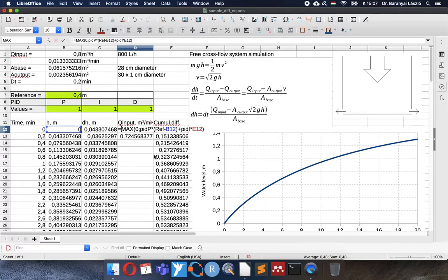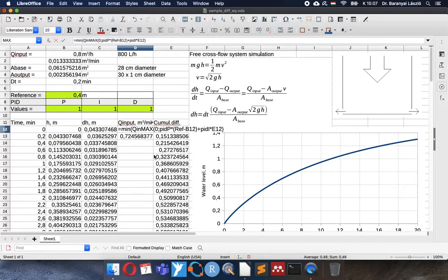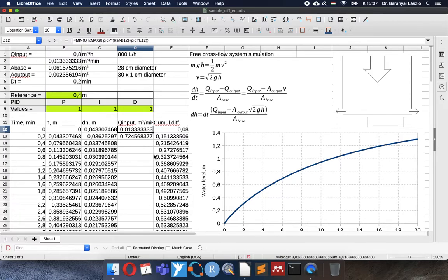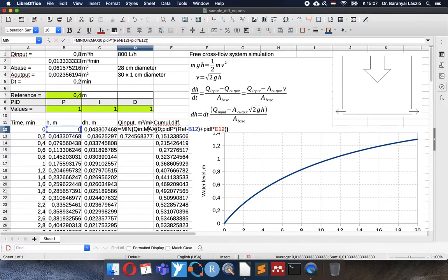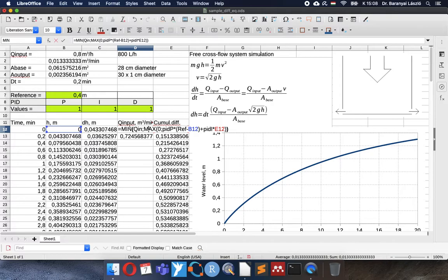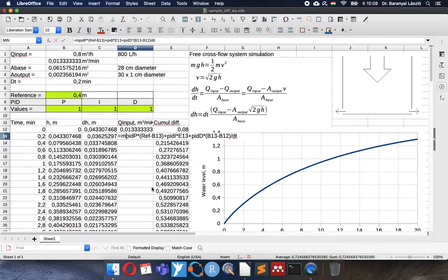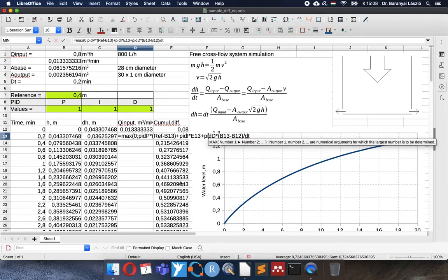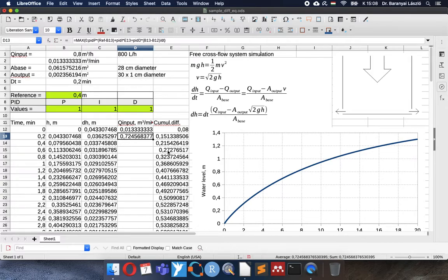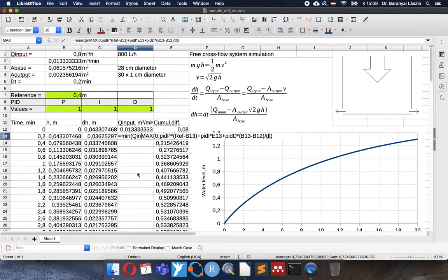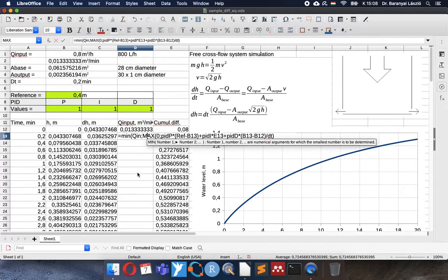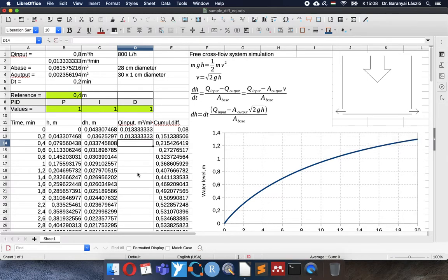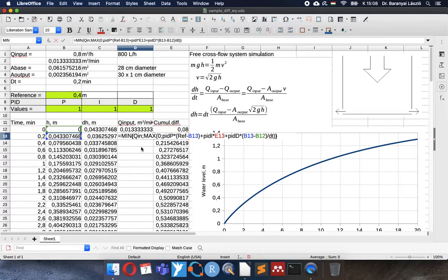So the other will be this was the maximum and then the minimum of input stream or the result of the calculation. And now you can see that yes indeed we use the combination of minimum and maximum functions to make a so-called bandpass filter or saturation filter which will restrict our calculation result between the input stream, the constant value and zero. I have to repeat it on the second line as well. So the maximum of zero and our calculation result will be the first step. And then I will enter again the input stream and the result of the previous one.